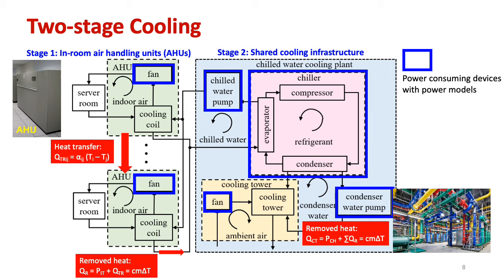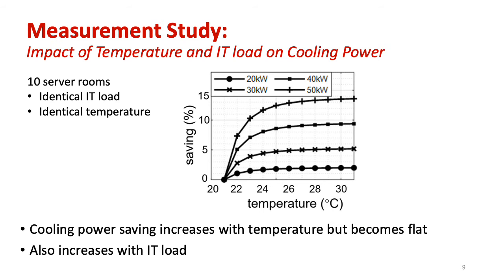We also adopt general power consumption models from an ASHRAE handbook for the cooling devices, including the fans of AHU and the cooling tower, water pumps, and the chiller plant. We conduct a set of measurement studies to gain insights. First, we investigate the impact of temperature set point and the IT load on the cooling power. We simulate 10 server rooms with identical IT load and identical temperature set points.